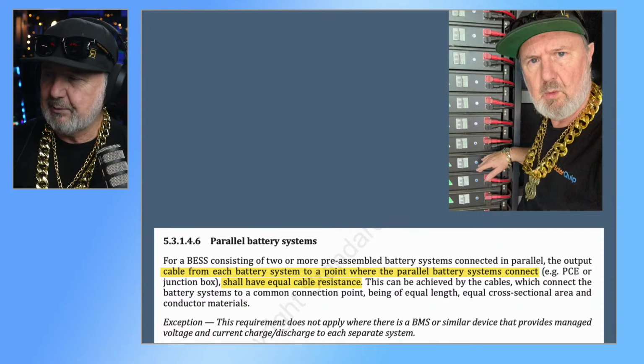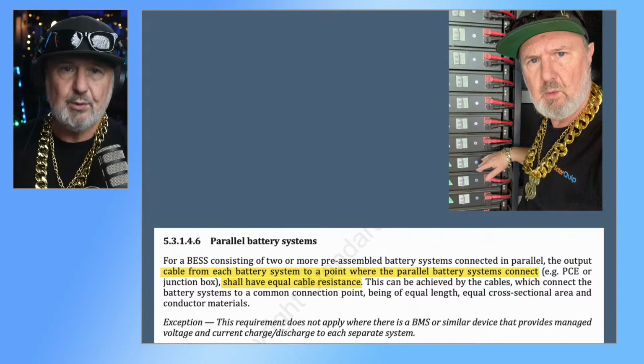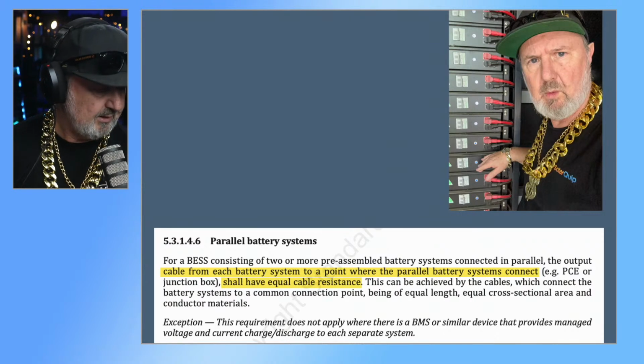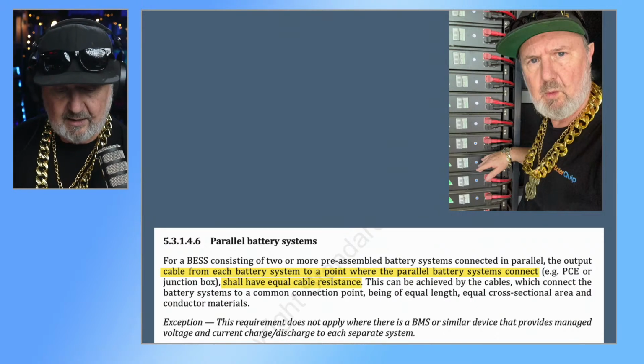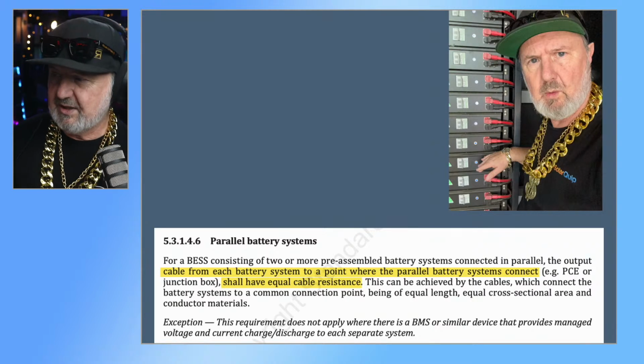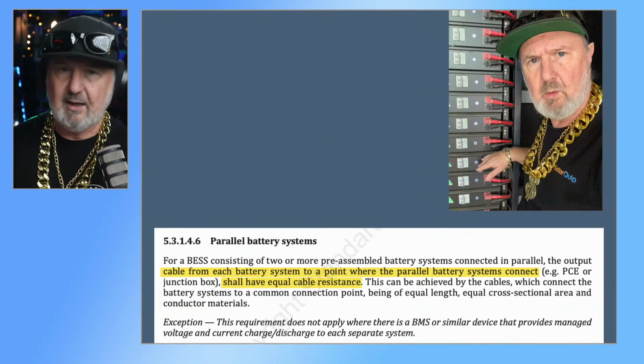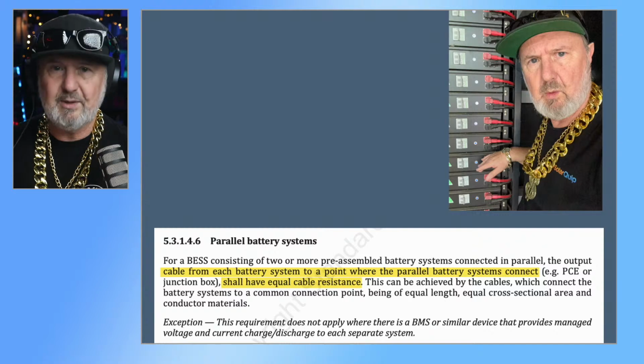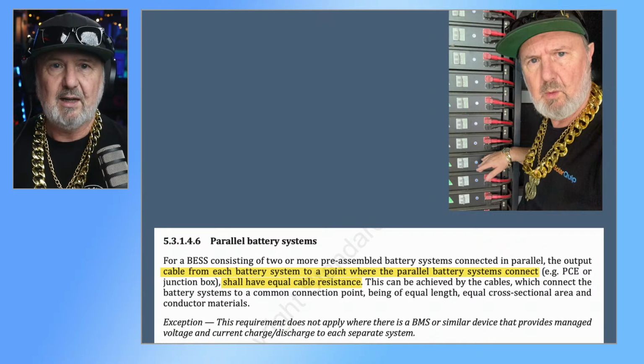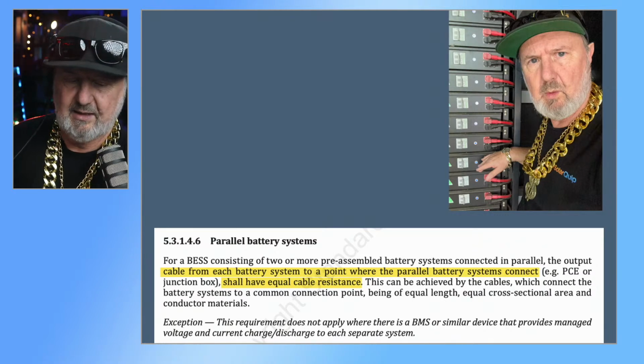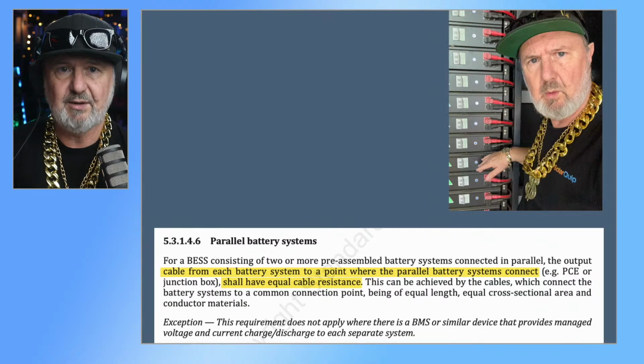So the output cable from each battery system to the point where the parallel battery system is connected, i.e. at the PCE or a bus bar, shall have equal cable length. Now, I've got some little drawings to explain this one. It's surprising that we've got a shall here. When I say surprising, normally shalls are reserved for safety, and this is kind of a performance consideration.